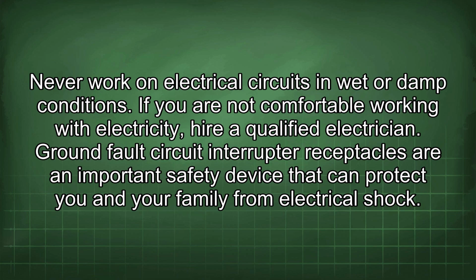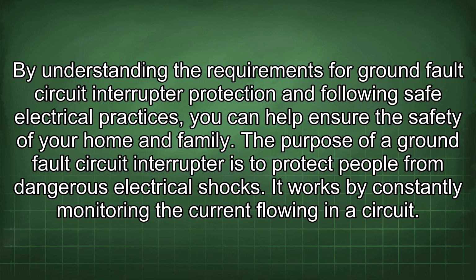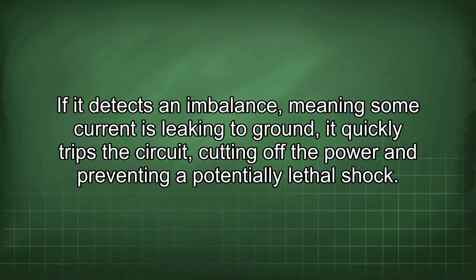Ground fault circuit interrupter receptacles are an important safety device that can protect you and your family from electrical shock. By understanding the requirements for ground fault circuit interrupter protection and following safe electrical practices, you can help ensure the safety of your home and family. The purpose of a ground fault circuit interrupter is to protect people from dangerous electrical shocks. It works by constantly monitoring the current flowing in a circuit. If it detects an imbalance, meaning some current is leaking to ground, it quickly trips the circuit, cutting off the power and preventing a potentially lethal shock.